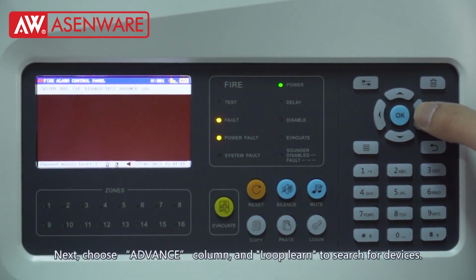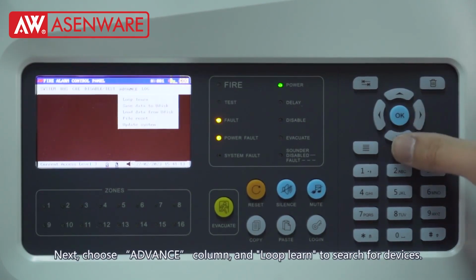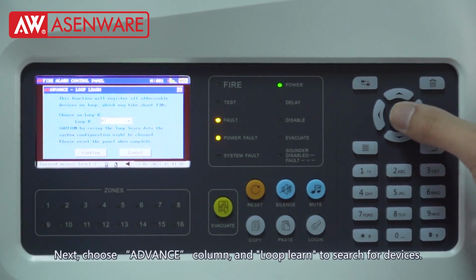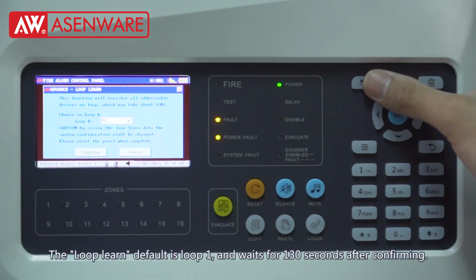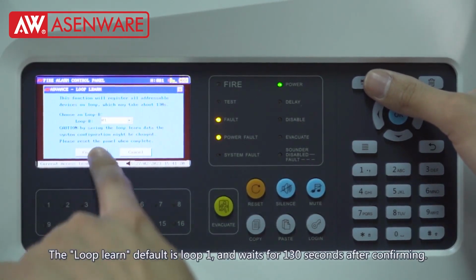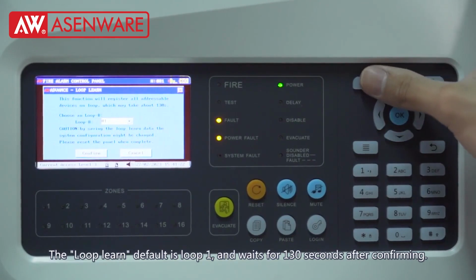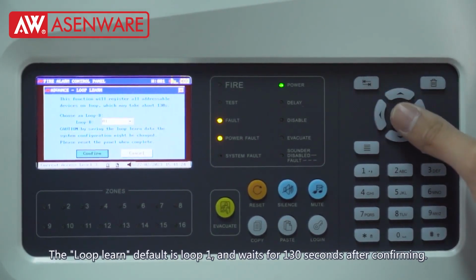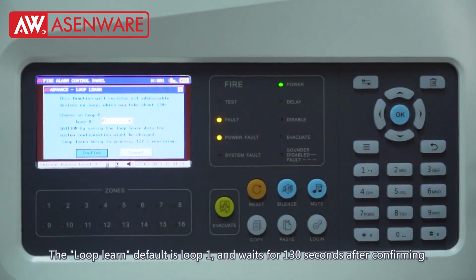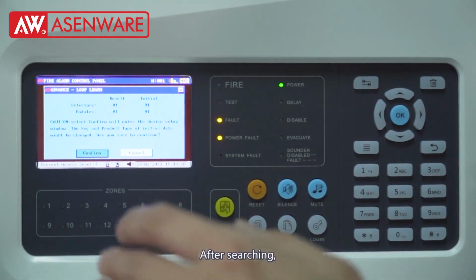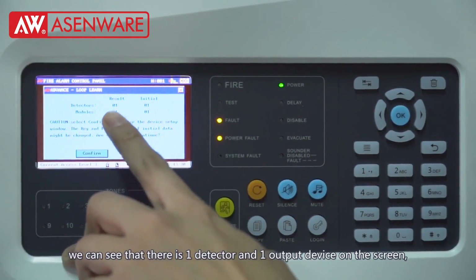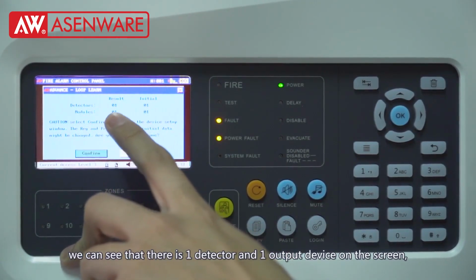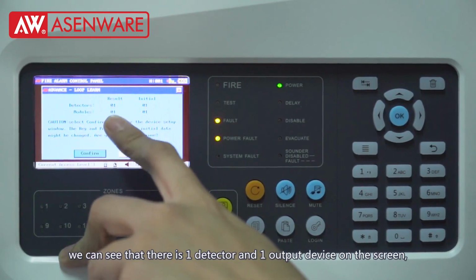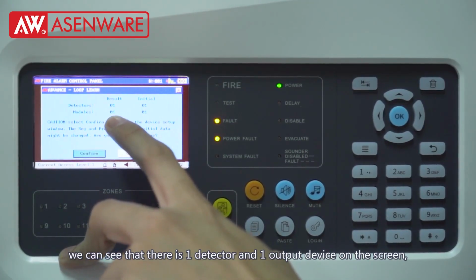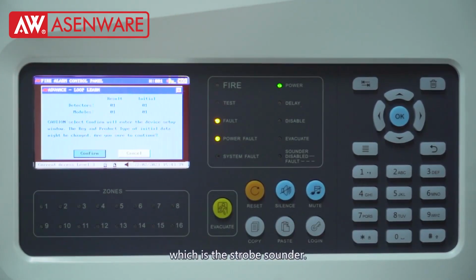Next, choose Advance column and Loop Learn to search for devices. The Loop Learn default is Loop 1, and wait for 130 seconds after confirming. After searching, we can see that there is one detector and one output device on the screen, which is the strobe sounder.